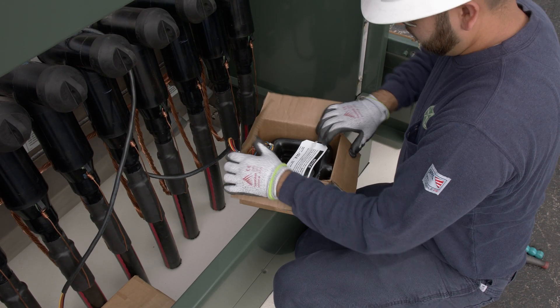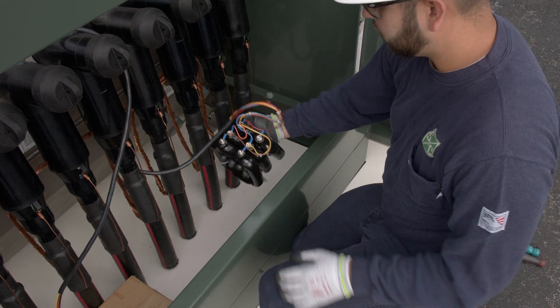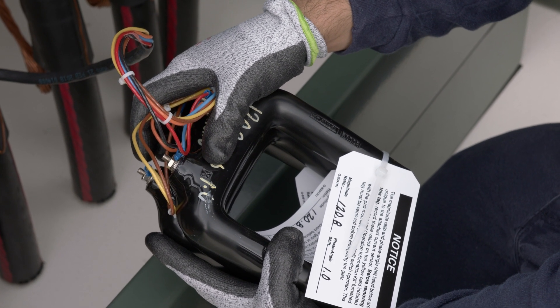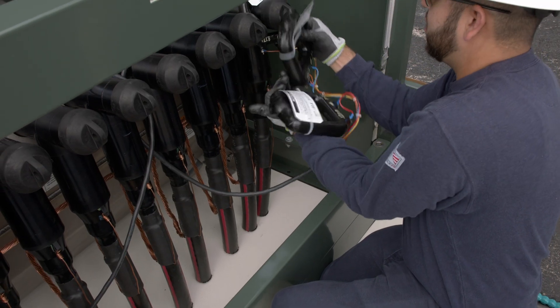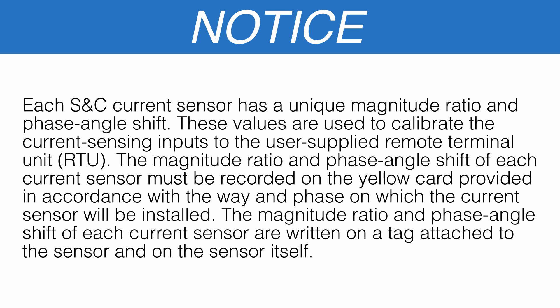To attach the sensors to the switchgear, remove the current sensors, hardware, and wiring harness from the box marked S&C current sensors. Connect the current sensors to the wiring harness as shown on the interconnection wiring diagram provided with the gear. Place each current sensor in front of the phase of the way on which it will be installed. Each S&C current sensor has a unique magnitude ratio and phase angle shift. These values are used to calibrate the current sensing inputs to the user-supplied remote terminal unit, RTU.